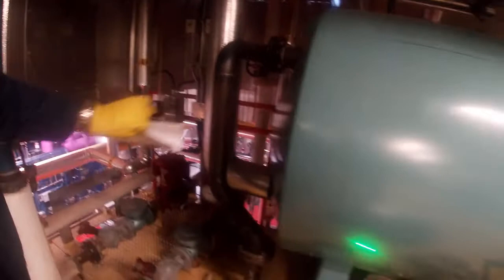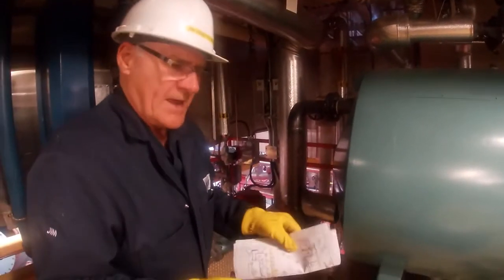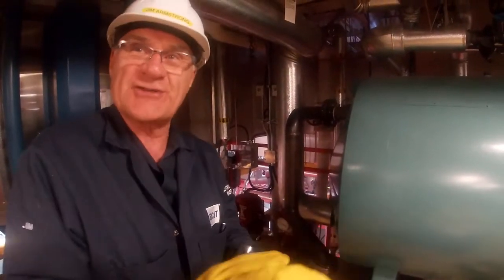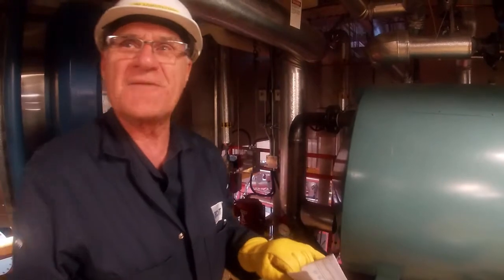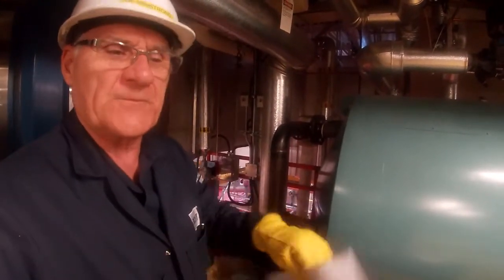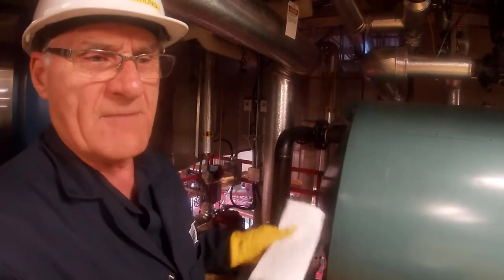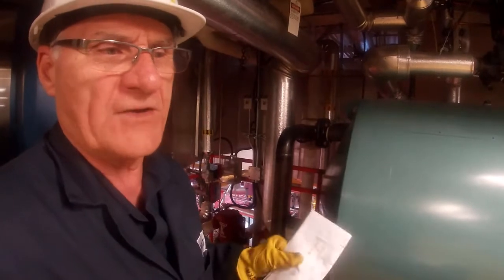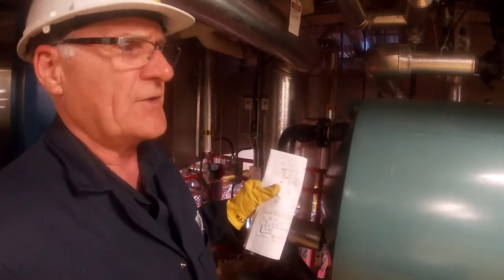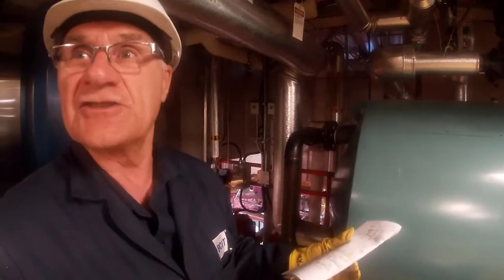That condensate comes down and comes into the vessel at the bottom. Inside there's a tube which has got holes through it, and it's a sparger tube, just like the spargers that you saw back on the evaporators, and it's allowing the hot condensate, which is going to flash into steam, to get back in here, because the condensate is coming back at probably about 105, 108 degrees C, and once it gets into this vessel, which is vented, it's going to flash into steam, or some of it will.